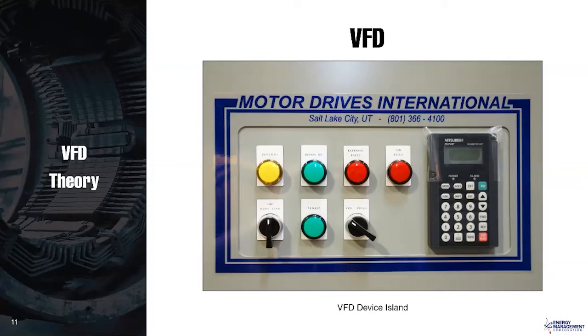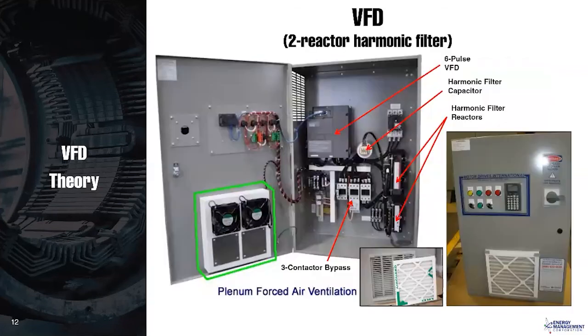We got a couple more slides. Let's go to the next slide. And this shows a VFD inside of a metal enclosure. This is how I recommend that you do it. And you can see that this VFD has a number of components. I won't go over those components because Barry's going to show you them in real time. But what I want to talk about is that filter on the lower right. We highly recommend a metal enclosure with a filter on it.